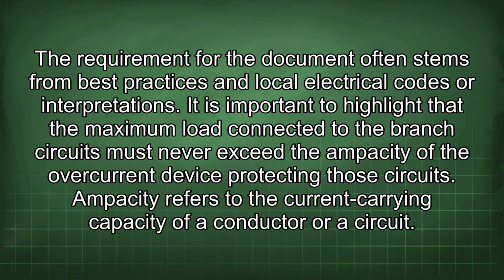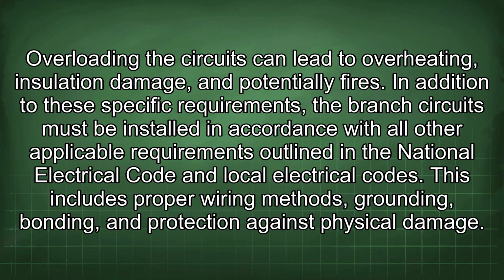The requirement for the document often stems from best practices and local electrical codes or interpretations. It is important to highlight that the maximum load connected to the branch circuits must never exceed the ampacity of the overcurrent device protecting those circuits. Ampacity refers to the current carrying capacity of a conductor or a circuit. Overloading the circuits can lead to overheating, insulation damage, and potentially fires.